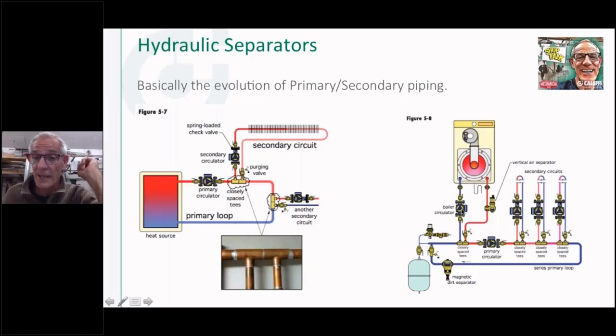Now, that being said, this circulator is pumping away from this point of no pressure change by this section of piping right here. So it does see this as pumping away on both these circulators, pumping away here into the boiler, which gives me that extra delta P in my high pressure drop type of heat exchanger. And this circulator is also pumping away from the point of no pressure change.